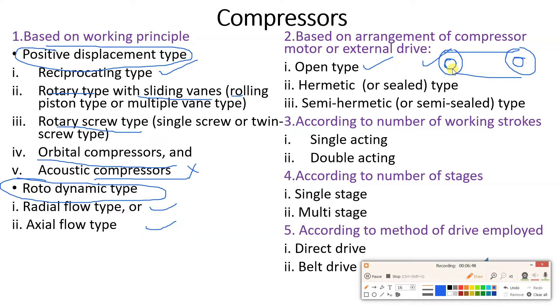In case of an open type reciprocating compressor, you can have single stage or multi-stage compression, and if multi-stage is there, we can have intercooling as well. So one cylinder with a piston reciprocating, discharge of the first cylinder goes through an intercooling arrangement and then to the inlet of the second compressor. Like this, in reciprocating compressors we can have multi-cylinder arrangements with or without intercooling.